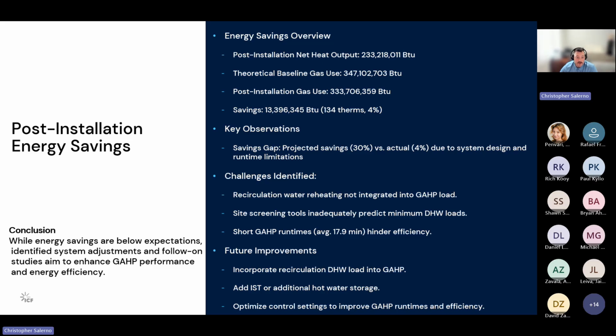Lastly, as future improvements, we also want to optimize control settings for the GHP's runtimes and efficiencies. Right now, the GHP really just has a standard tank stat on the buffer tank and the water glycol loop that it has, which is basically telling the GHP to turn on and off. So there are areas to improve, based on more advanced controls, to be able to control the behavior of the GHP a little bit more.